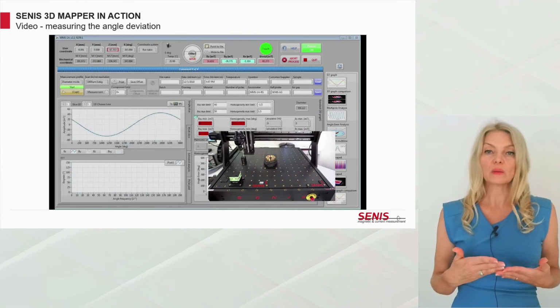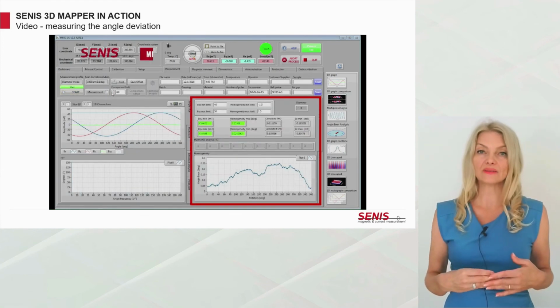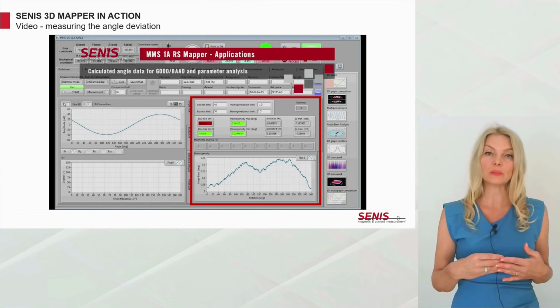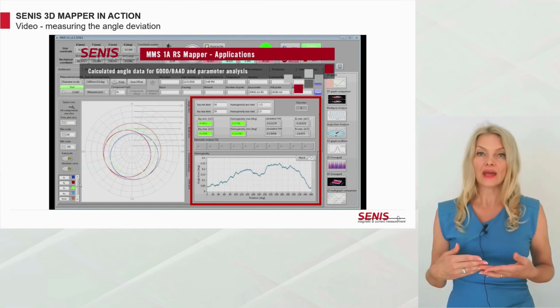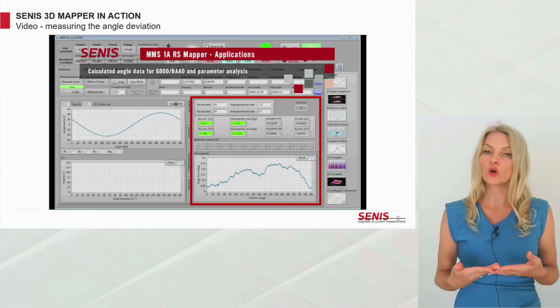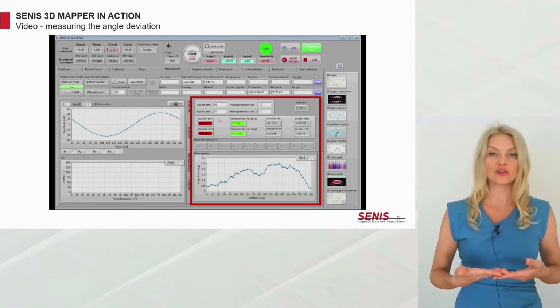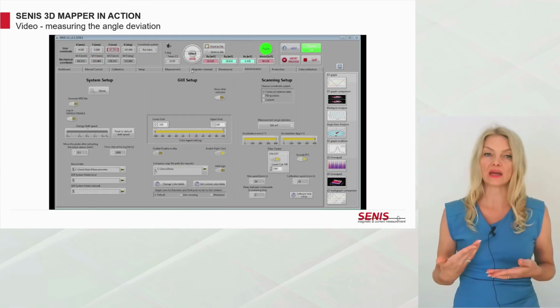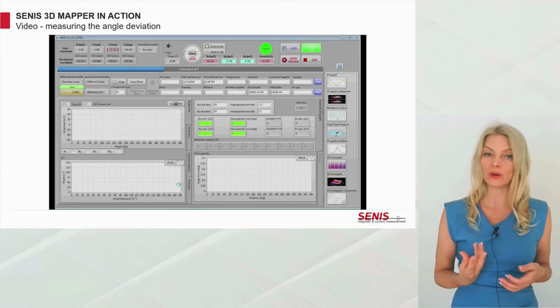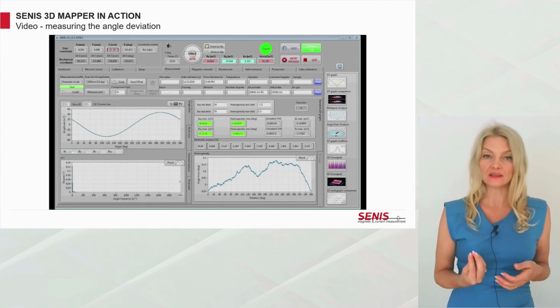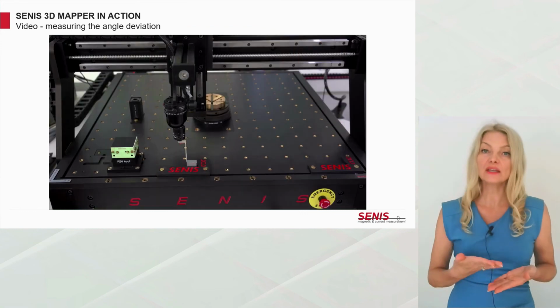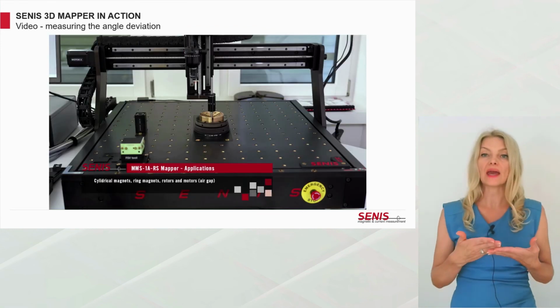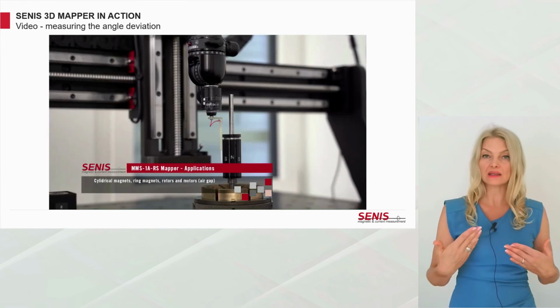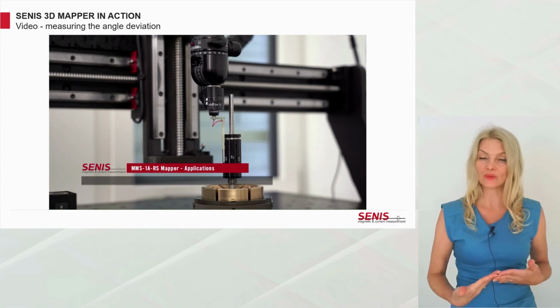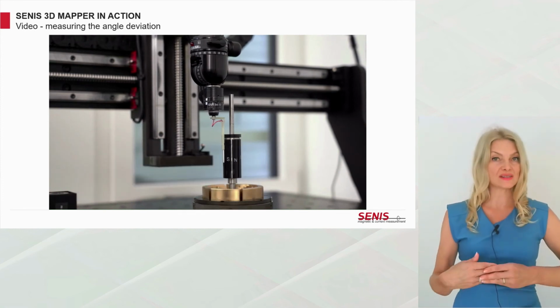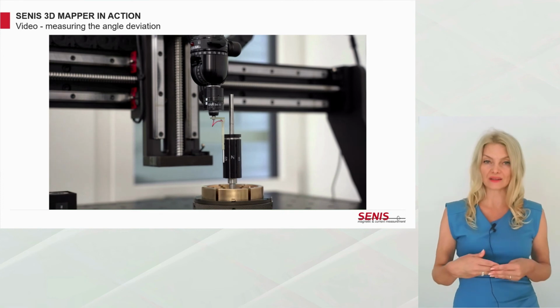The real magnetic angle is calculated as arc tangent of Bx, By. At the same time, the encoder mounted under the rotary stage measures the angle of rotation of the mapper, giving the ideal angle. The difference between the real and the ideal angle gives the angle deviation. The entire scan process takes only a couple of seconds.